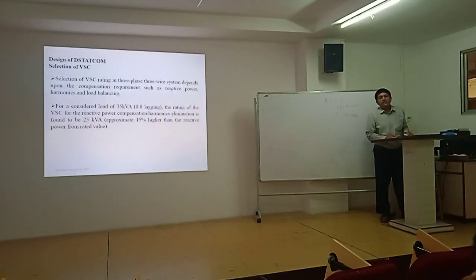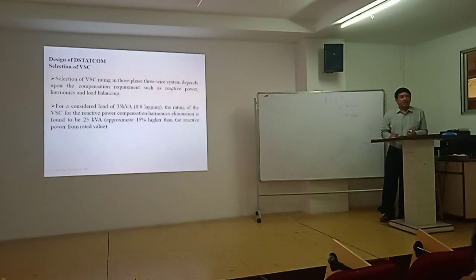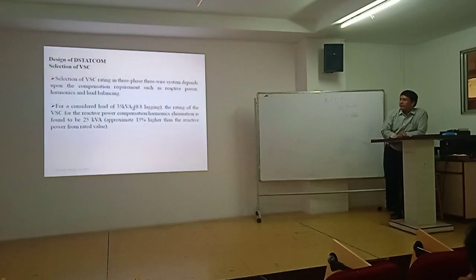Assume that load is 35 kVA. Some load is there, na? And we are going to design the compensator based on the highest rating only. So assume that the consumer has a 35 kVA, 0.8 power factor load, and they want a shunt compensator. So you can see power factor 0.8. Now you can find out the reactive power from this one.